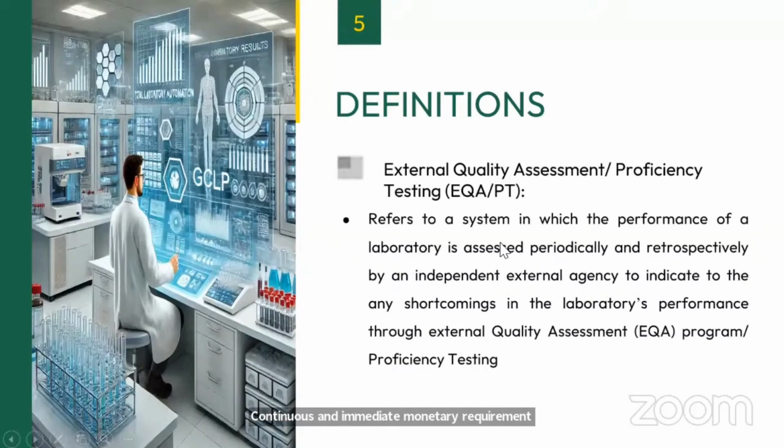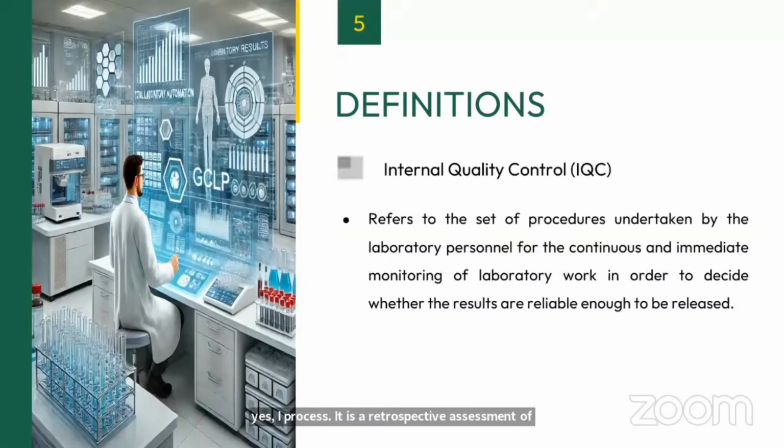Whereas in external quality assessment, you can see what is the difference. It is periodic and retrospective. It is not continuous, it is not a real-time process. It is a retrospective assessment of your laboratory's performance. Whereas internal quality control is continuous and immediate monitoring. It is in real time. We monitor the performance of our laboratory and decide whether the results generated are reliable and can be released for appropriate patient care. So that is the importance of internal quality control.